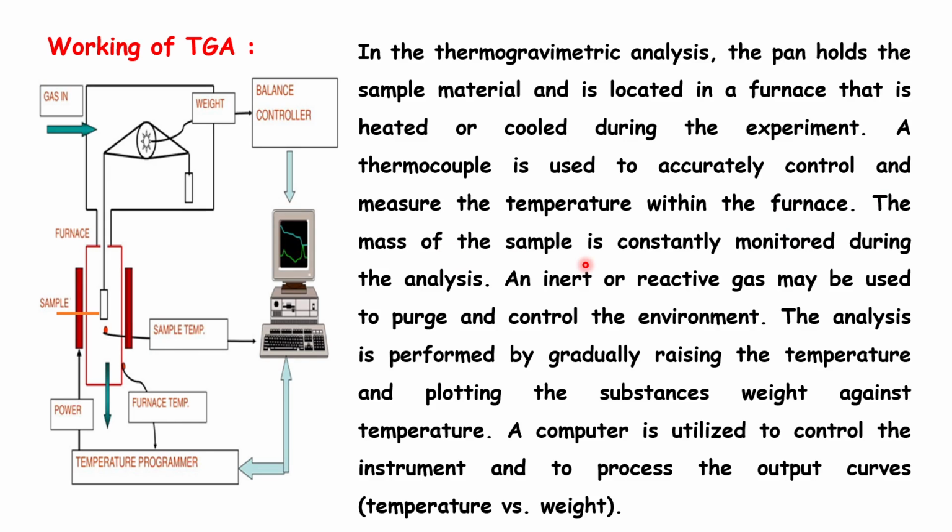The mass of the sample is constantly monitored during the analysis by using the precision balance, and inert or reactive gases may be used to purge and control the environment.